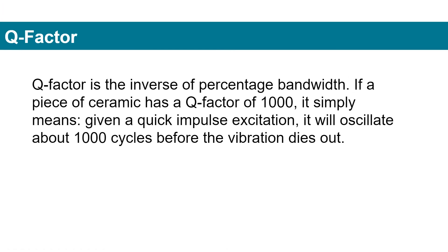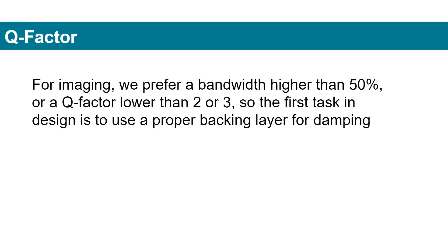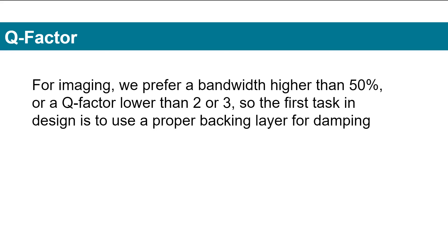Q-Factor is the inverse of percentage bandwidth. If a piece of ceramic has a high Q-Factor of 1000, it simply means that given a quick impulse excitation, it will oscillate about 1000 cycles before the vibration dies out. Most piezoelectric materials have a high Q-Factor. For imaging, we prefer a bandwidth higher than 50%, or Q-Factor lower than 2 or 3. So the first task in design is to use a proper backing layer or layers for damping or preventing backward emission — that is, lowering the Q-Factor.